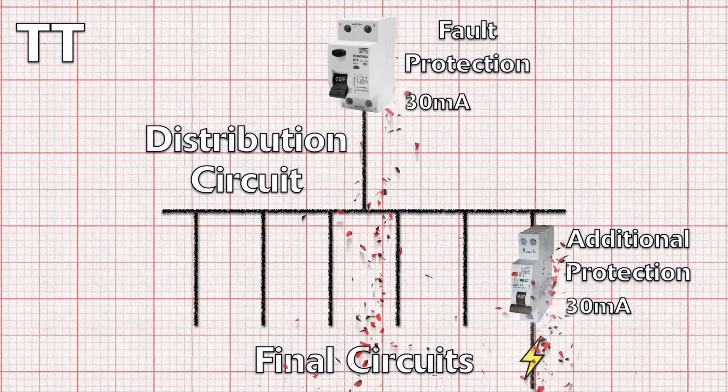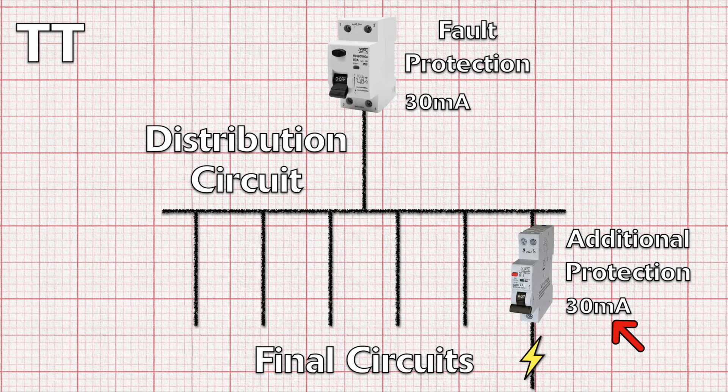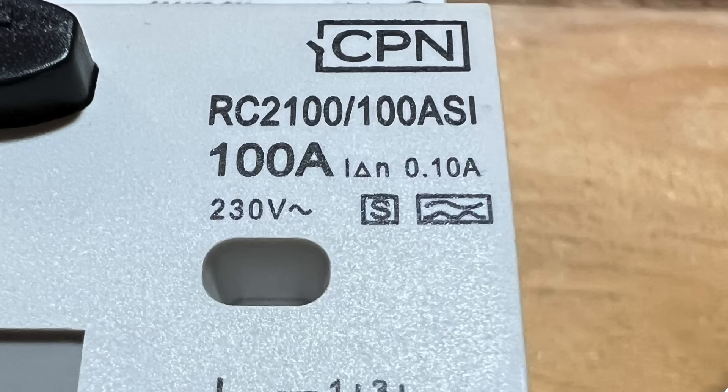So if the RCD protection on the final circuit has a rating of 30 milliamps, the upstream RCD protection on the distribution circuit should be 90 milliamps or above. Most manufacturers will produce a time delayed RCD at 100 milliamps rather than 90 which is even more acceptable.